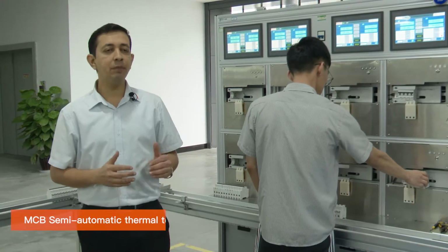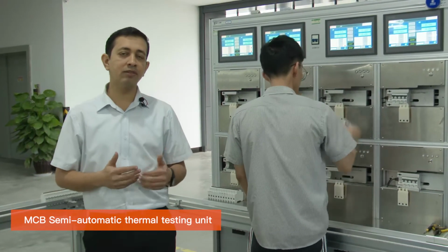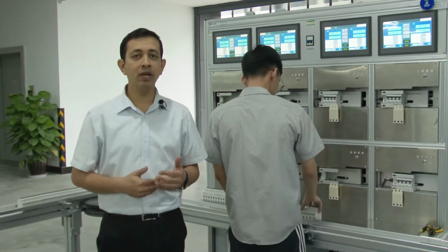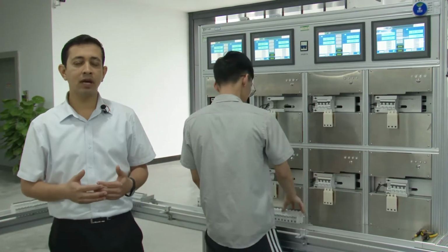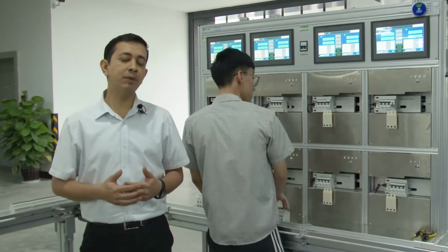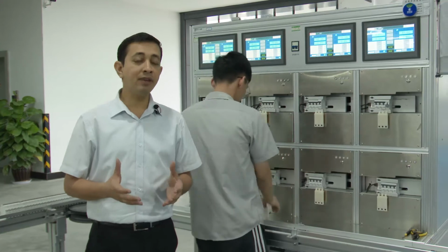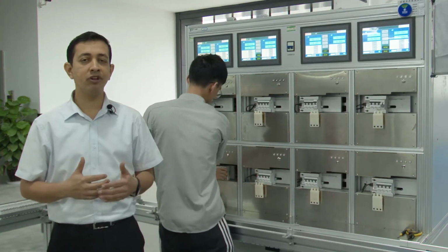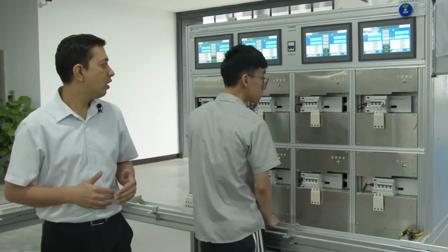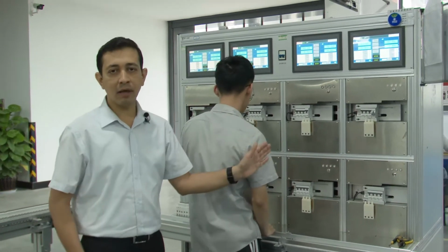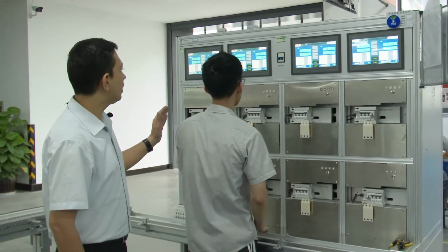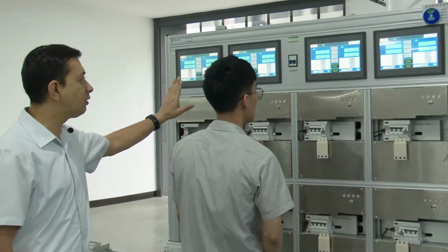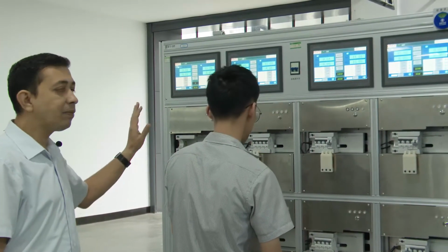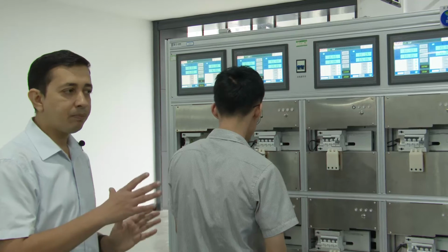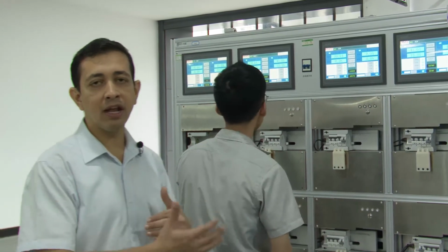As we have seen in the previous machine, the MCBs are cooled after thermal calibration. Now the MCBs have to be re-verified to see whether the calibration process is okay or not. You can see it is a semi-automatic machine, wherein the thermal calibration verification is done, and after the thermal calibration is qualified, it goes for the multipole coupling in the next station.